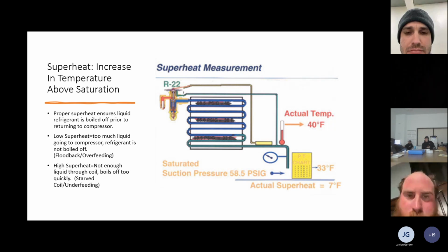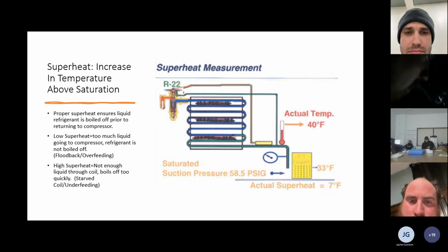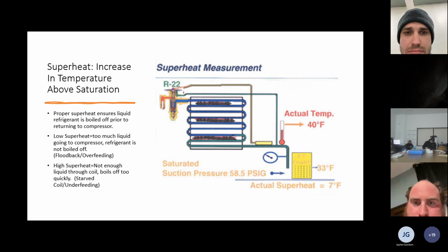If you look at a PT chart for that refrigerant, it shows you this swing of temperatures. So FieldPiece goes off the middle. I want to say Testo goes off the low glide. I never set superheats with my Testo gauges. They are horrible. So that's just one thing to remember too.